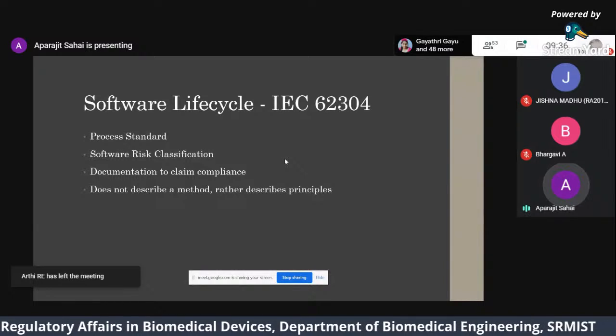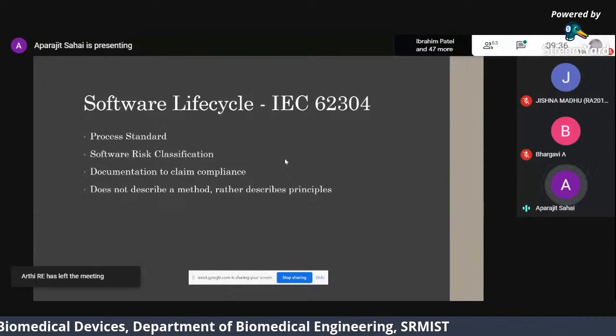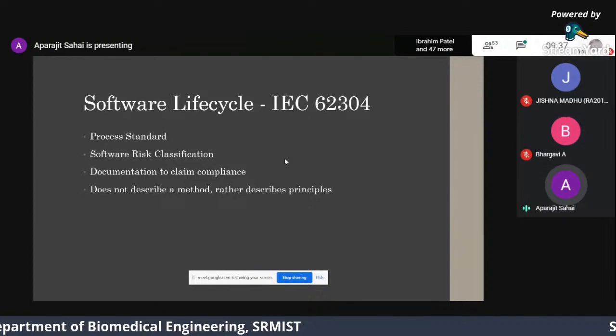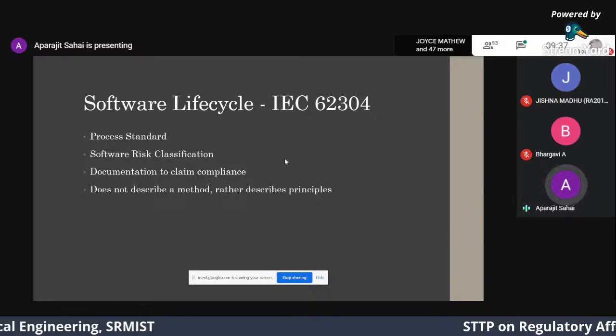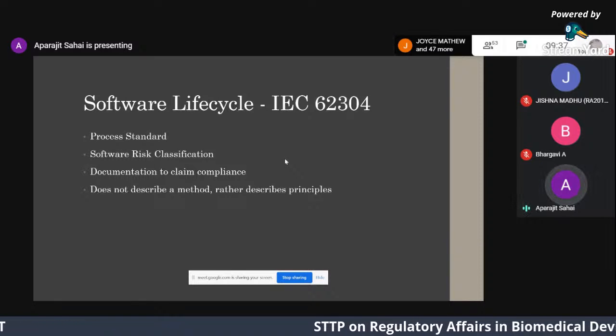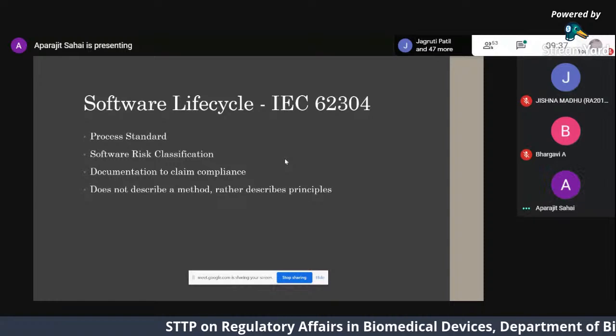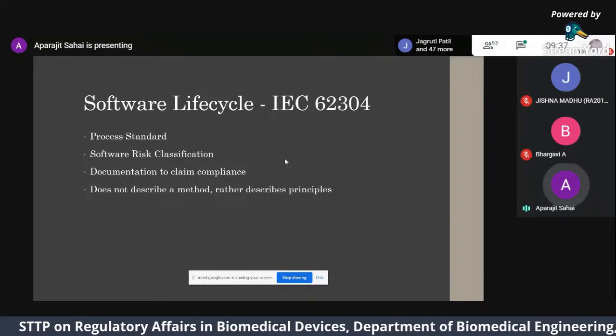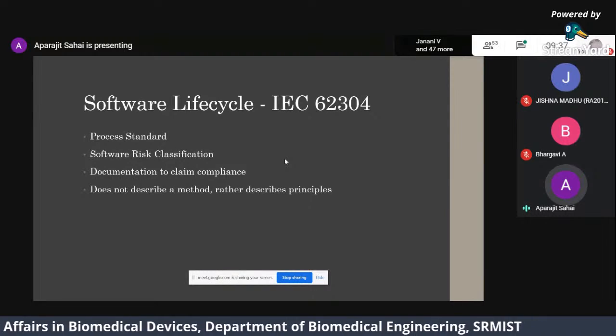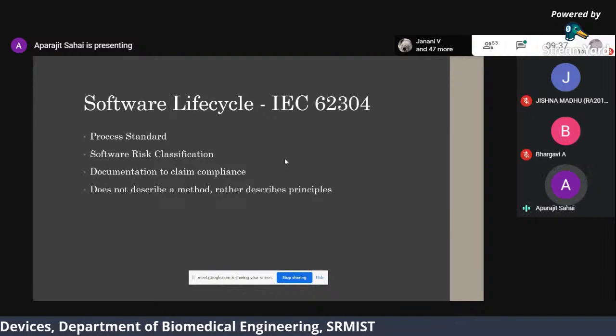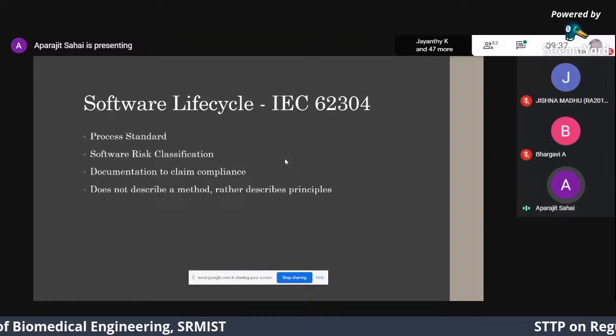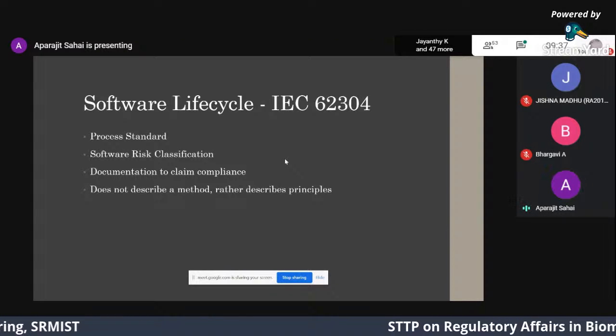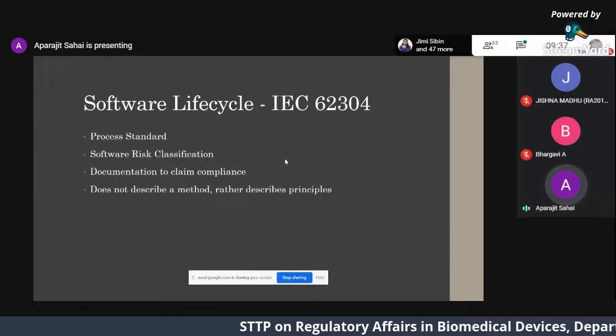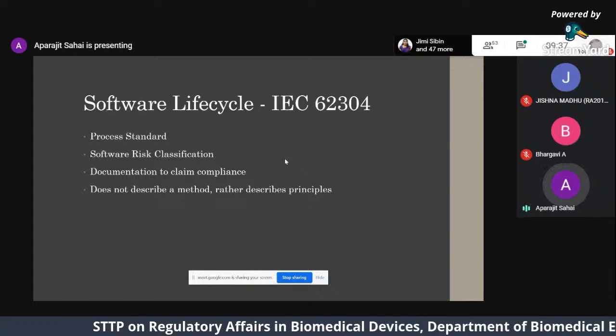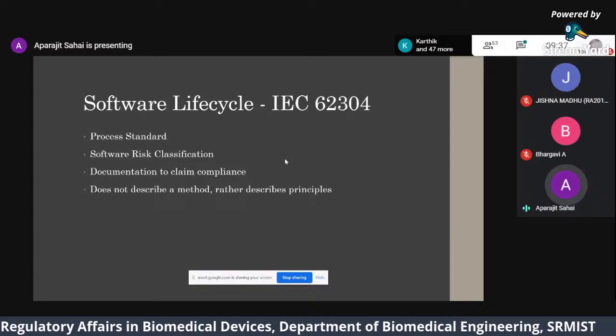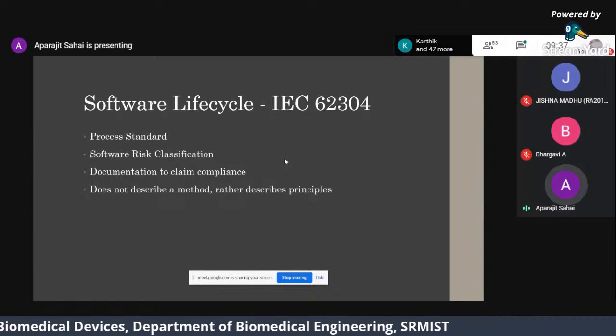Check in your jurisdiction if they have a different way of classifying medical device software. The classes in 62304 allow you to downgrade the class. Let's say a device is class C, you implement risk control measures. You can bring the risk class down to B and then subsequently A, hopefully, in some cases. But the FDA doesn't allow that. If you have software that is high risk, then it will remain high risk. Of course, you have to mitigate, but in general, it will remain high risk, and that's what the FDA would want you to treat it as. You can't change it to a moderate risk.